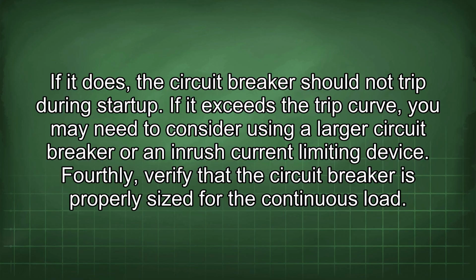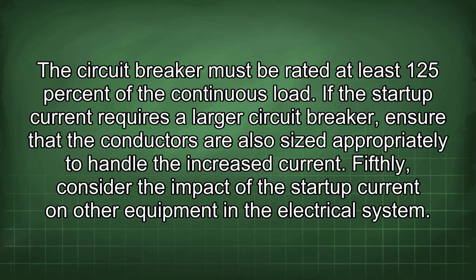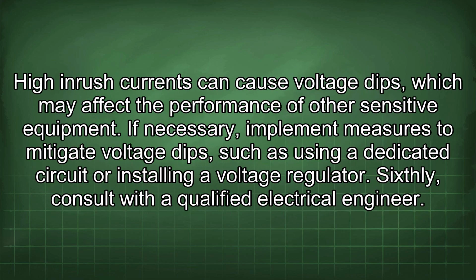Fourthly, verify that the circuit breaker is properly sized for the continuous load. The circuit breaker must be rated at least 125% of the continuous load. If the startup current requires a larger circuit breaker, ensure that the conductors are also sized appropriately to handle the increased current. Fifthly, consider the impact of the startup current on other equipment in the electrical system. High inrush currents can cause voltage dips, which may affect the performance of other sensitive equipment. If necessary, implement measures to mitigate voltage dips, such as using a dedicated circuit or installing a voltage regulator.